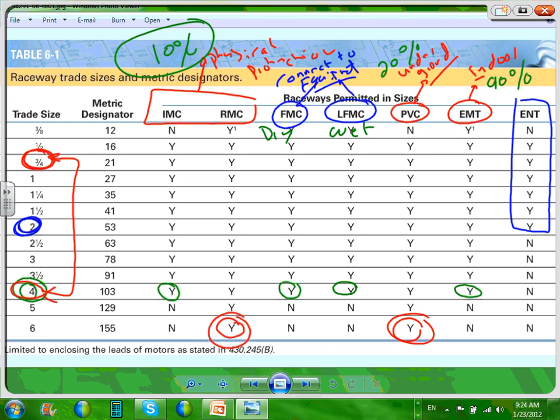One application, guys, on a project we had, I wasn't the engineer on that: if you have an electronic equipment lab and you want to minimize the interference with radio frequency, you want all your wiring methods to be non-metallic, because metallic acts as an antenna and brings noise to your equipment. So all your receptacles here will be wired with non-metallic boxes as well as non-metallic conduit. This becomes an interesting way of wiring. You can wire the whole building with non-metallic.